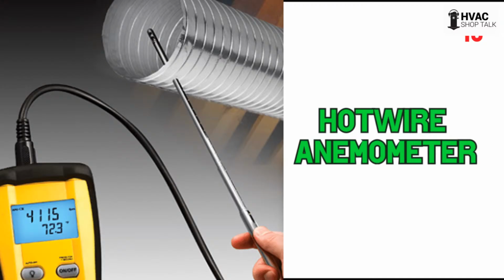So what you do, in the picture here for the podcast people, is basically what looks like a piece of spiral duct. They've cut a hole in it, and this probe is sticking through that hole. What you'll do is move it across the diameter of the duct, and you may do this in 3 locations because you want a nice look all the way across that ductwork. You don't want to measure just across the middle because that might be a dead zone - it's like, well, it's very slow here.